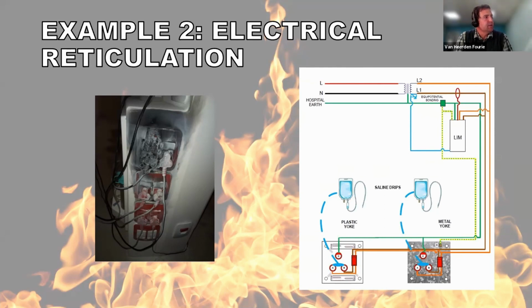So in that case, you'll see the photo on the left where we actually had it heat up severely, and luckily it didn't cause a fire. But it's a great risk in terms of a fire risk and losing a part of your electrical reticulation that supplies equipment that is used on a patient. On the switch socket outlets with the metal base plate or the metal yoke, there's an earth connection on the metal plate that is bonded with the earth further down the line, and which feeds back into the line isolation monitor.